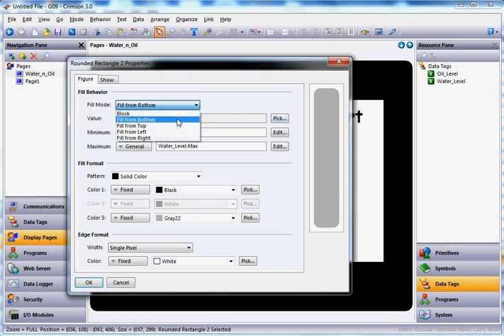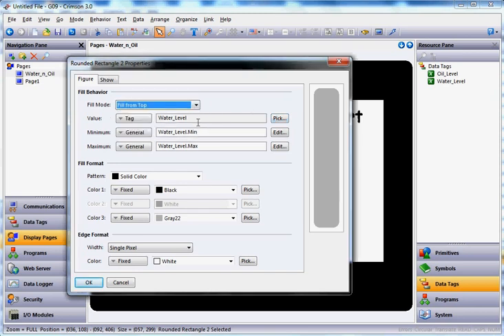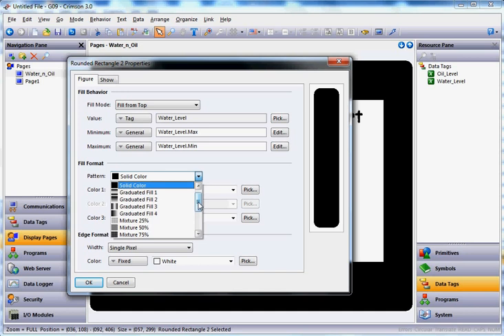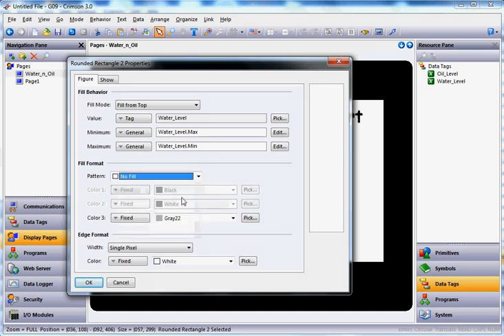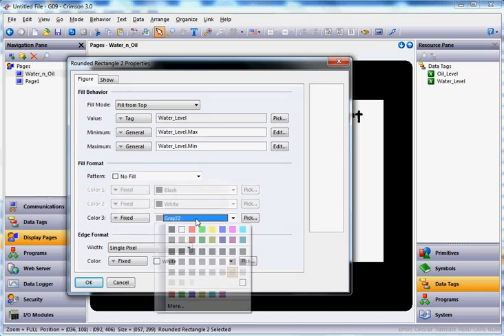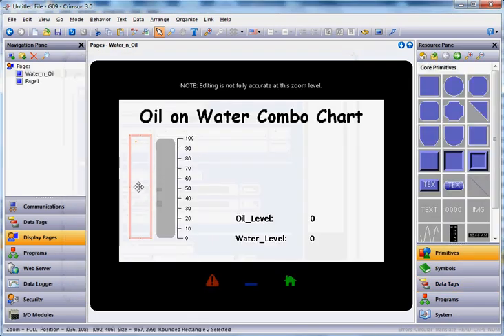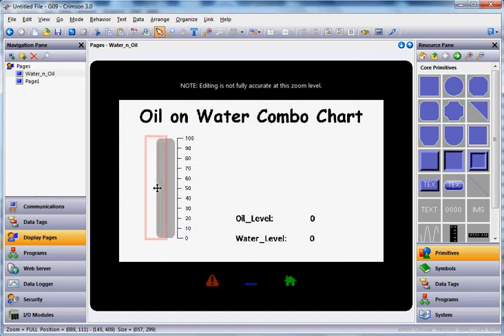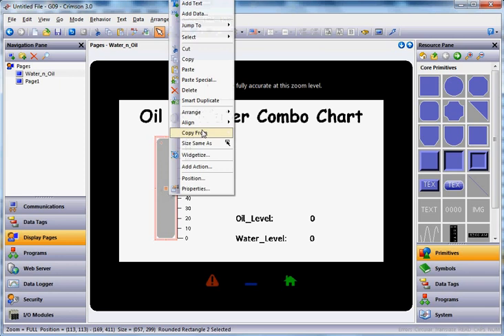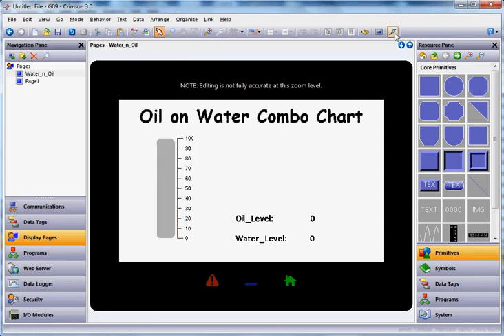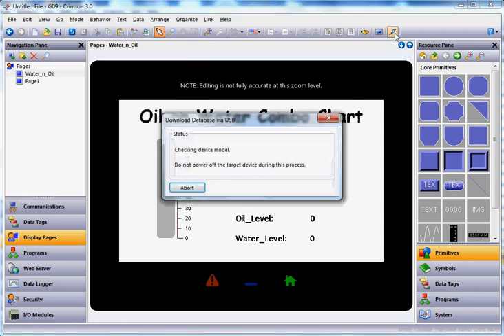With the water level, I'm going to choose to fill from the top and instead of the min and max being like this, I'm going to invert this so this is going to become the max and this is going to become the min. And then instead of a solid color here, I'm going to hit the pull down and tell this particular primitive that you know what, I don't want you to fill with the color at all except this color down here, I'm going to use blue. So it's going to be kind of weird but it's going to come down from the top leaving the blue. It's going to look a little weird but this is kind of a facade that we're going to make happen. We'll click okay and then I'm going to take this guy and I'm going to move it over this guy like this, kind of position it right on top of this unit here and I'm going to right click and make sure that that guy is always in the front. Alright, let me go ahead and download this guy to the screen and let's see what happens.